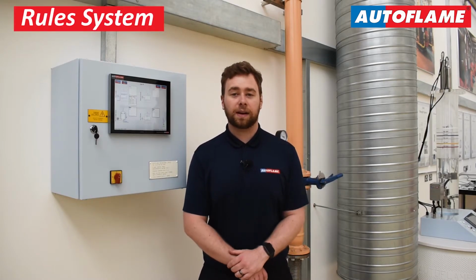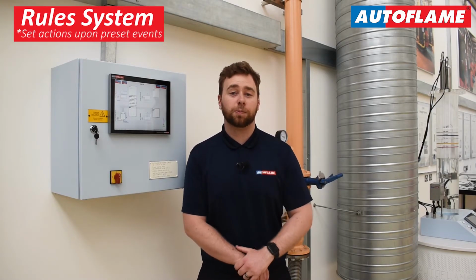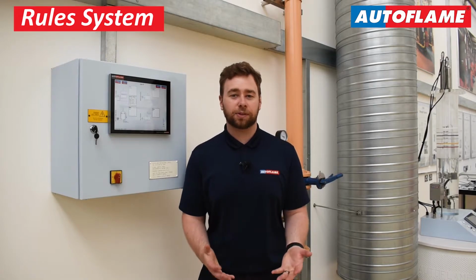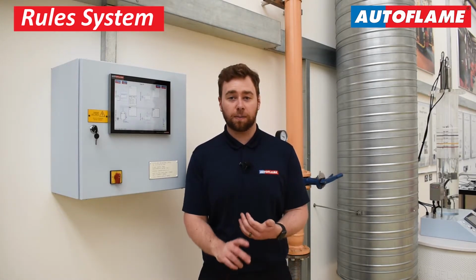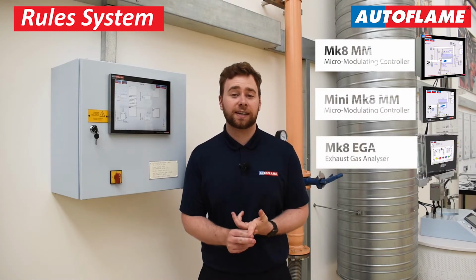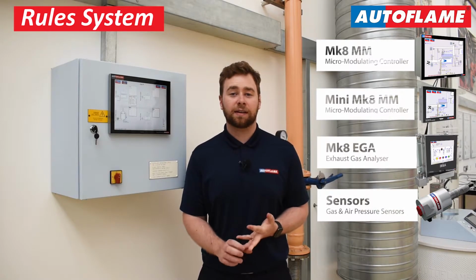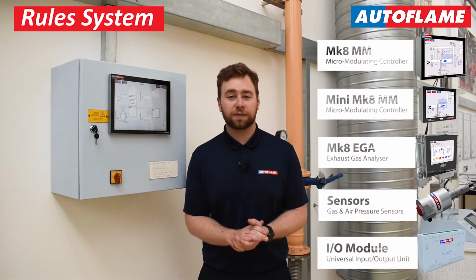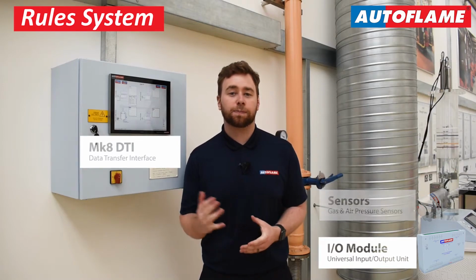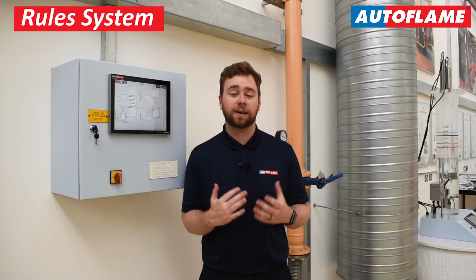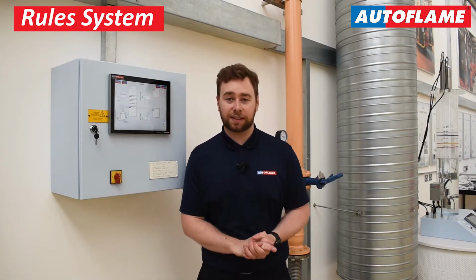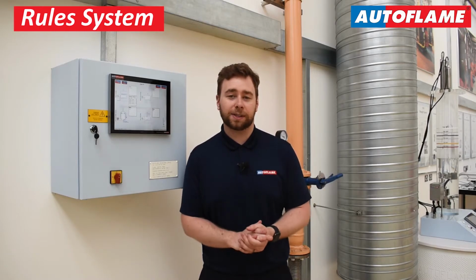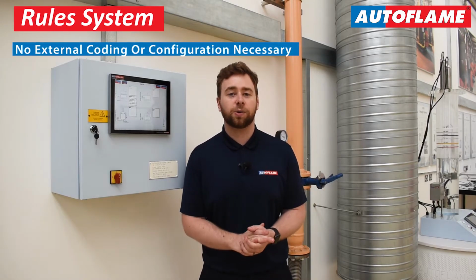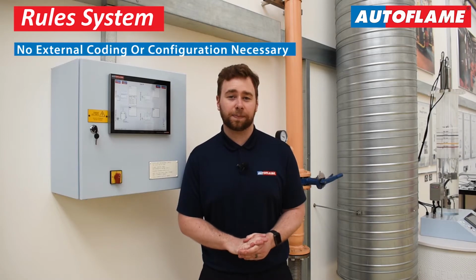On the Mk8 DTI, the rules system allows the user to set actions upon preset events. Inputs to these rules can be from any connected MM, EGA, gas or air pressure sensor, input-output module, or even the DTI itself. Now, the parameters of these rules have been set by us within the boundaries of the system architecture, unlike a PLC, so no external coding or configuration is necessary.